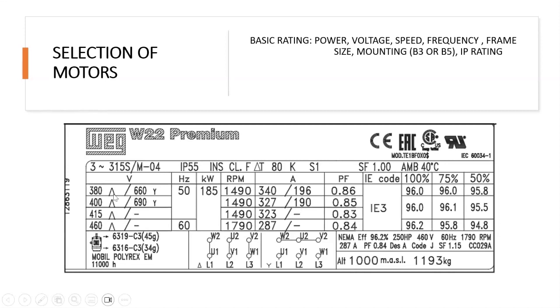On the screen is a typical nameplate data of a motor. There's something I want us to note. On this nameplate, we have the insulation class, and we also have the temperature rise. The insulation class is F, and the temperature rise is seen as being 80 degrees Celsius. We will look at this also in the course of our presentation. You can also see the type of grease, the bearing numbers, and the running hours after which greasing must be done.